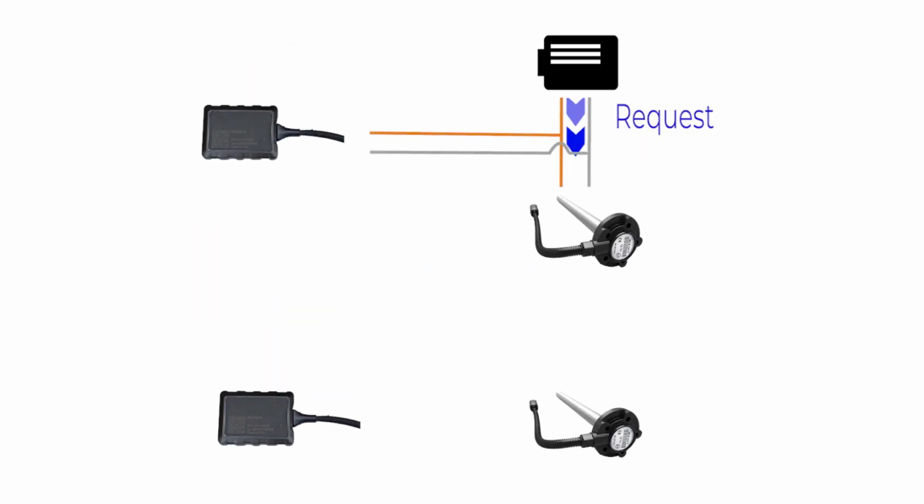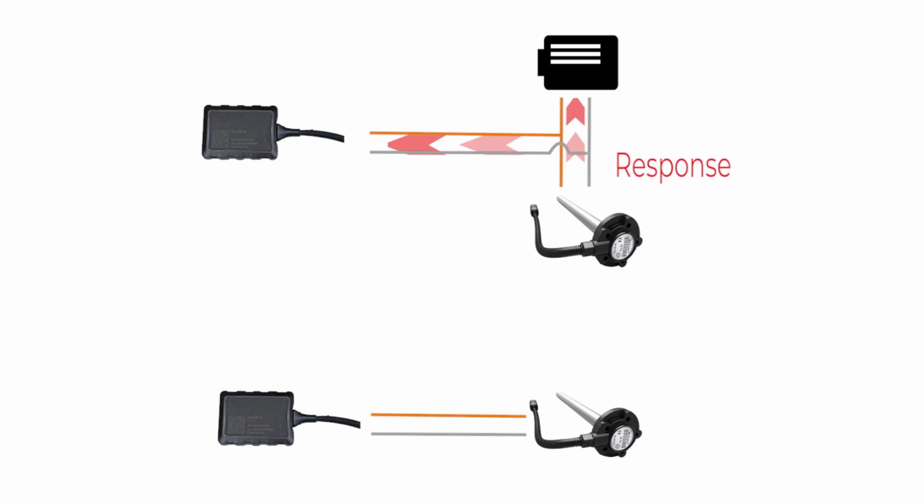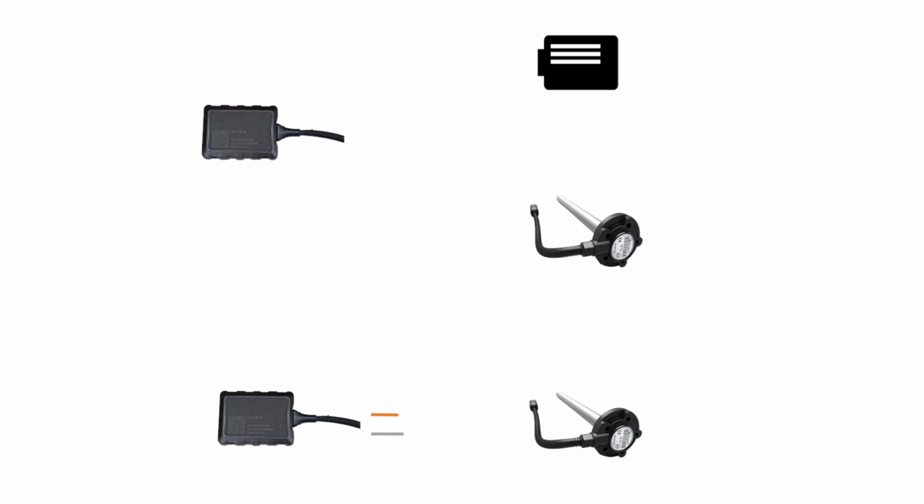In this setup, the lines RS485 A and B, the orange and the white wires of the sensor, must be connected to the lines RS485 A and B of all other devices, including the indicator. If you plan to connect the wired sensor only to the I5, so there will be no GPS tracker or other external device, then the I5 must be configured in the RS485 active mode.